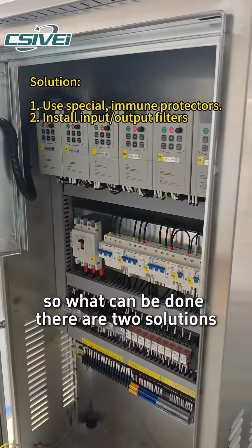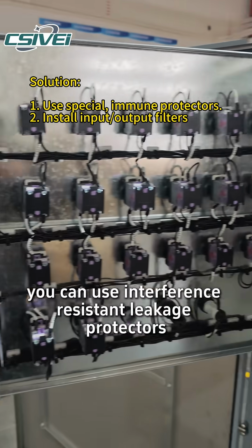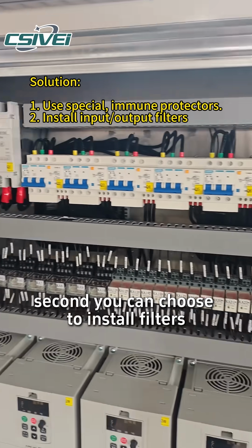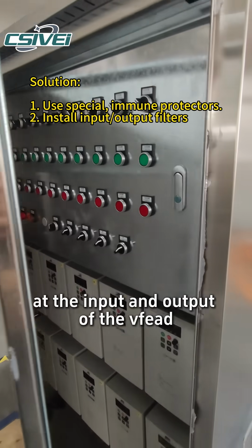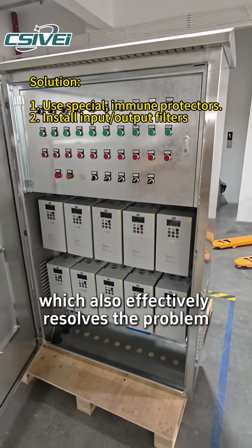There are two solutions. First, you can use interference-resistant leakage protectors to address this issue. Second, you can choose to install filters at the input and output of the VFD, which also effectively resolves the problem.